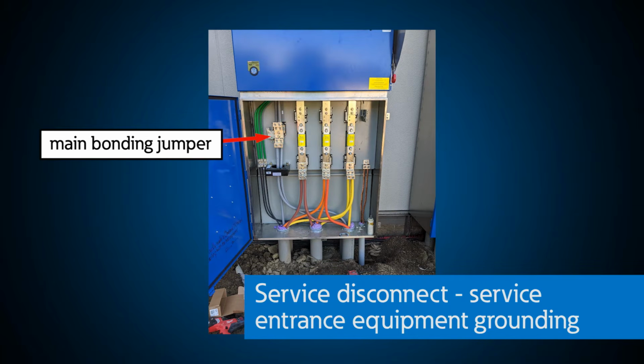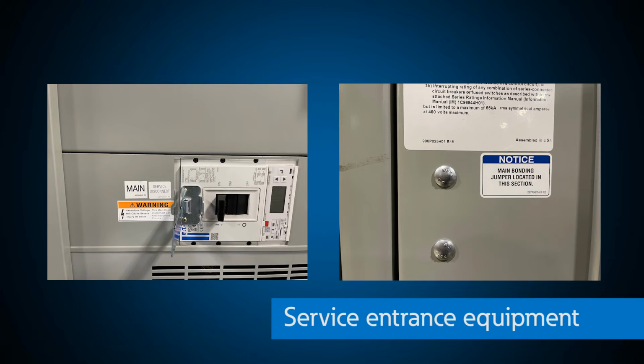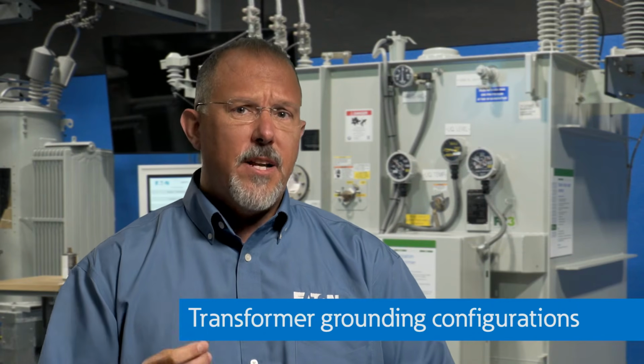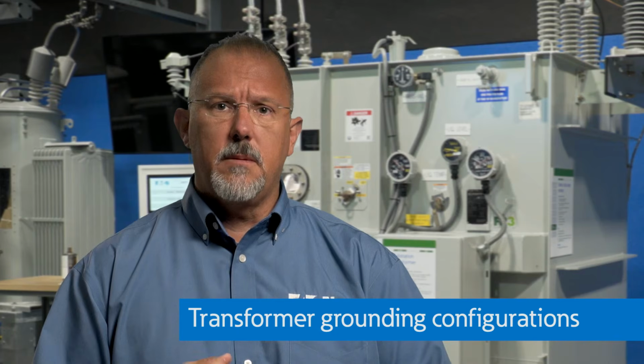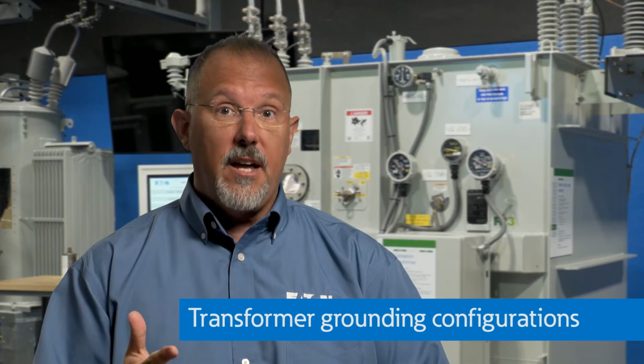For larger systems like the pad-mounted transformer or the switchgear, if the utility owns the transformer, we would see the neutral to ground bonding jumper installed inside our switchboard or switchgear, and we would bring the grounding electrode conductor into that service equipment. That is why it is clearly marked as service entrance equipment or suitable for use as service entrance equipment, because it has the capability to bond the neutral to ground inside that equipment. The transformer is a very important piece of the power system puzzle because it establishes the voltage levels and the neutral point on the power distribution system.